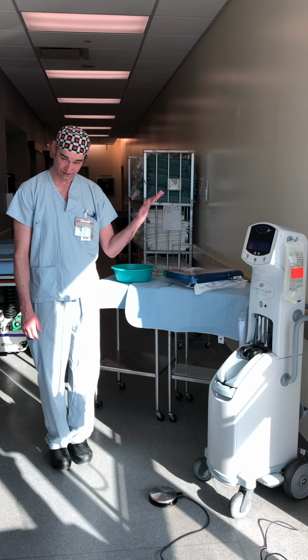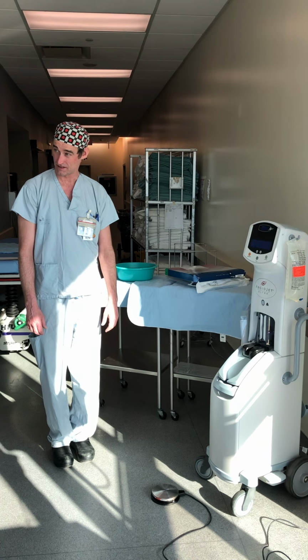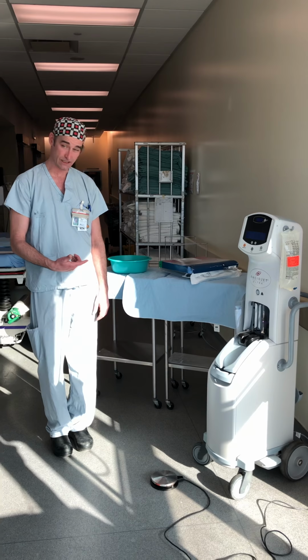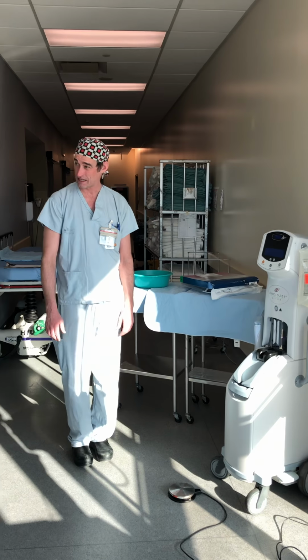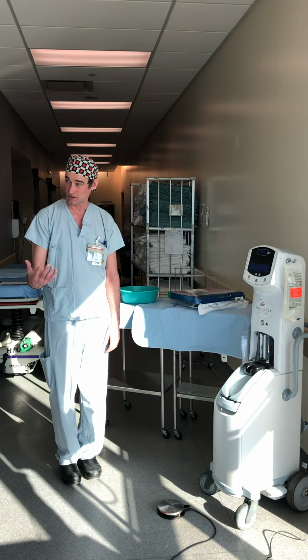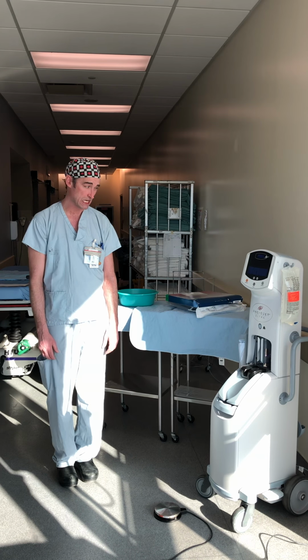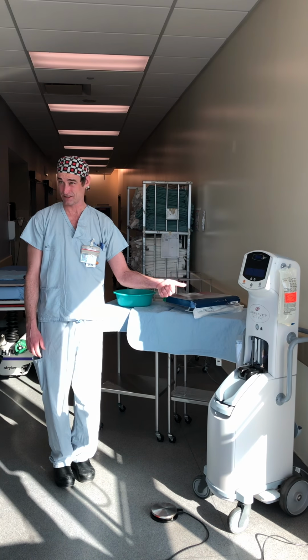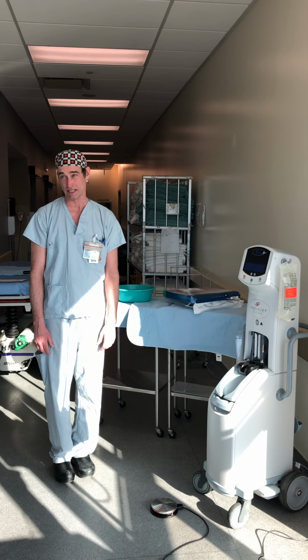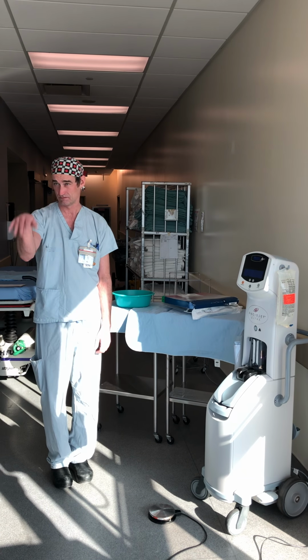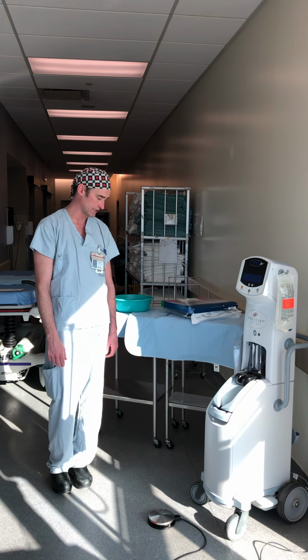This machine is a mechanical thrombectomy device, as you know, right? The indications for this over an export catheter would be a large diameter vessel with a very heavy thrombus burden. Typically you're not going to see this used unless your vessel's probably in the 4.5 to 5.0 range. Otherwise it's much safer and easier just to use the regular export.